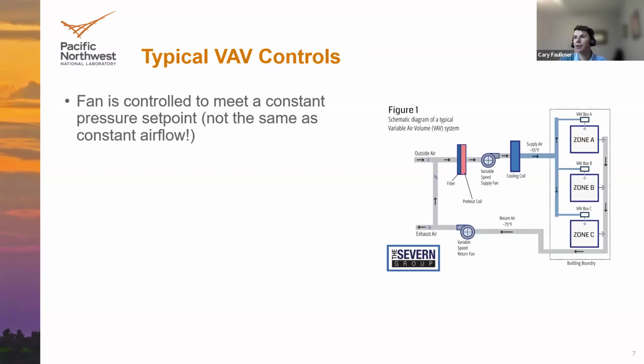So now let's talk about some of the controls related to both the air handling unit and terminal units of the VAV systems. So first, that fan is not necessarily going to be controlled to meet a constant airflow set point, of course, because it's going to be variable, but it's going to be controlled to meet a constant pressure set point, which is different. In particular, the static pressure reading for the air handling unit control is going to be based on how open or closed those dampers are. As the dampers open more, the static pressure will drop as there's less resistance to push the air through the system, which tells the fan it needs to work harder to meet that pressure set point and thus provide more air, which is what the zones are telling you when those dampers are open, that they need more air.